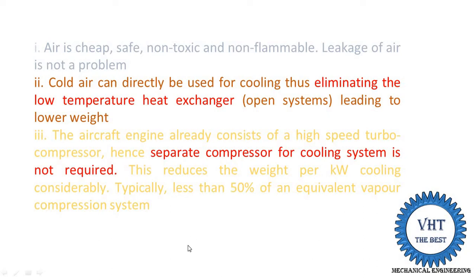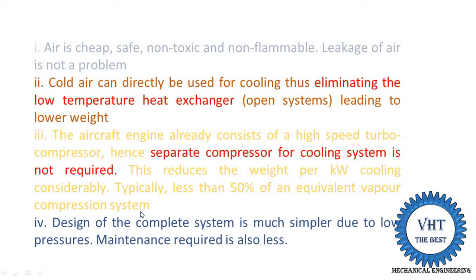The last reason is that the design of the complete air refrigeration system is much simpler and lower in cost. The VCRS system operates at higher pressures in the condenser, whereas the air refrigeration system operates at lower pressure. Lower pressure means smaller diameter tubing, lower wall thickness, and lower maintenance cost. These are the reasons why air refrigeration systems are used in aeroplanes and VCRS systems are not.